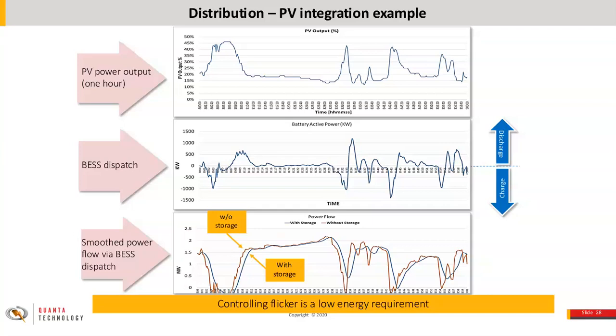The conventional fixes for that can be expensive—it means stiffening the circuit, increasing the conductor size to decrease resistance and the sensitivity of voltage to PV production. A very small battery located with the PV can be used to change the rate of change. If you look at the bottom graph, you can see the storage just slows down the changes that occur with the photovoltaic fluctuation. It doesn't take a big battery.